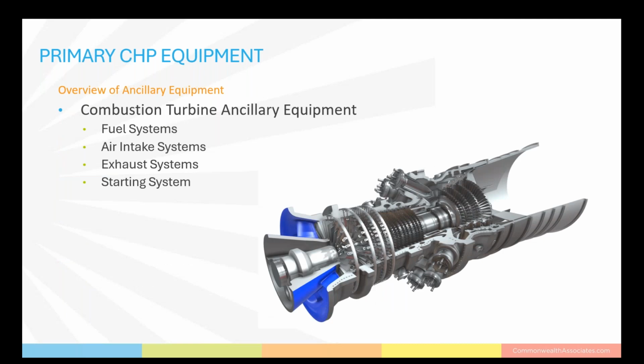Three important things to consider on a GA for a gas turbine generator are to ensure there's adequate clearance for maintenance, inspection, and repair. Consider the location of the fuel systems, air intake, and exhaust systems, and allow for easy access to engine controls, instruments, and safety devices. Depending on the size of a combustion turbine, it may require any or all of the following ancillary equipment to be part of the general arrangement: fuel pumps, fuel filters, fuel heaters. In regards to air, you need air filters, air compressors, intercoolers. You have the exhaust stacks, exhaust silencers, and you will have starters, batteries, and charging systems.